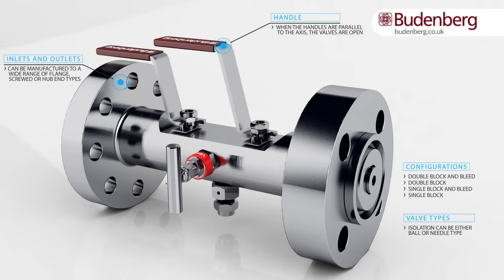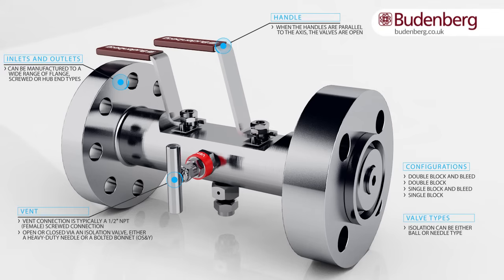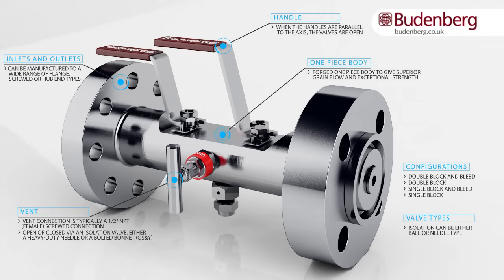The vent connection is typically a half-inch NPT female screwed connection, open or closed via an isolation valve — either a heavy duty needle or a bolted bonnet OS and Y. The forged one-piece body gives superior grain flow and exceptional strength. Residual media is released only after the vent and drain plug have been opened.